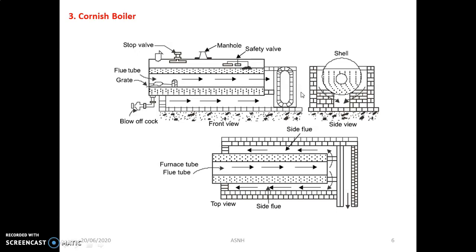The products of combustion pass from the fire grate forward over the brickwork bridge to the end of the furnace tube. They then return by the two side flues to the front end of the boiler and again pass to the back end along the bottom of the boiler to the chimney. This return path is the main specialty of the Cornish boiler, where combustible gases pass through and return again from the back section.